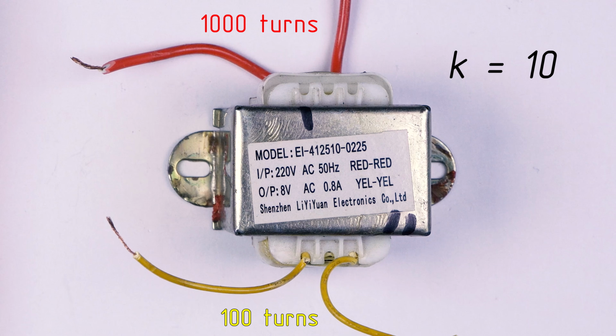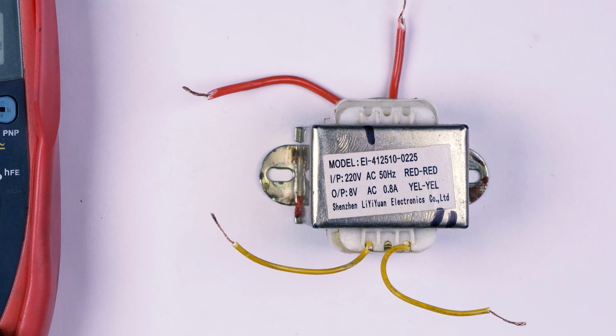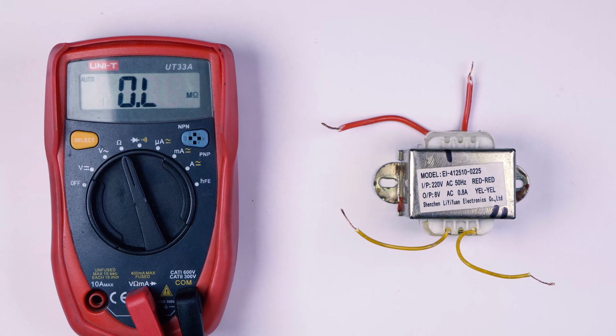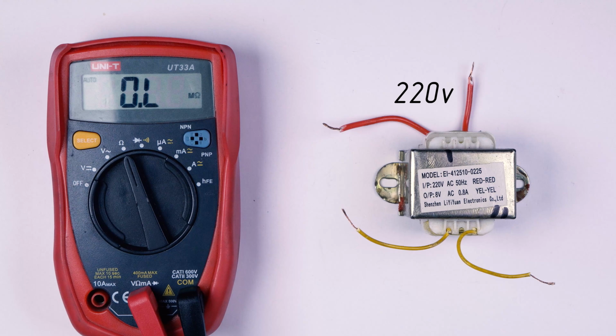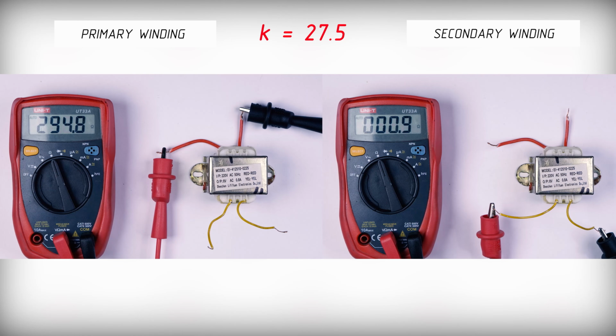If the number of turns is all that counts, it looks like we can figure out the transformation ratio by coil resistance, which is directly proportional to wire length. Let's check it in this transformer. If it inputs 220 volts and outputs 8 volts, its transformation ratio should be 27.5. However, the winding resistance ratio, as we can see, is more than 300. How to explain it?